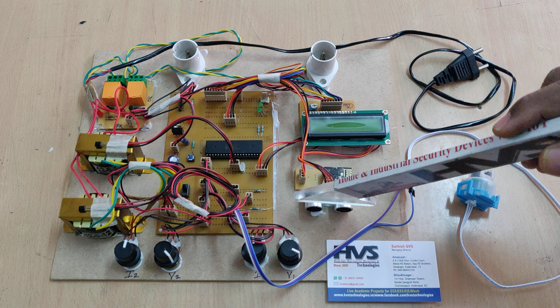The ultrasonic sensor measures the distance from an object surface; it doesn't know whether it's liquid or solid. When placed on top of the transformer, it checks the distance to the oil. Considering the transformer height as 100 centimeters, when it's filled with oil the distance from the oil surface to the sensor is very small, so it's considered as high oil level. As the oil level decreases, the distance automatically increases.